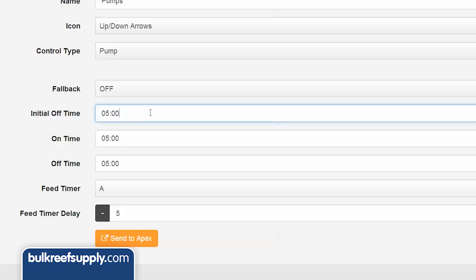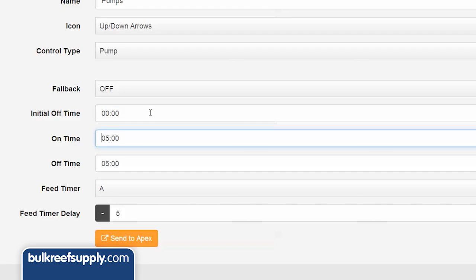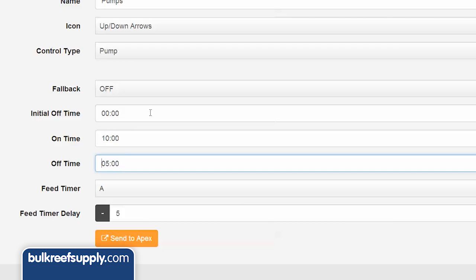However, you can still use this function for return or equipment pumps if you want. Set the initial off time to zero, the on time to basically anything — I will use ten minutes — and the off time to zero. This means the pump will come on immediately, stay on for ten minutes, and then never turn off.